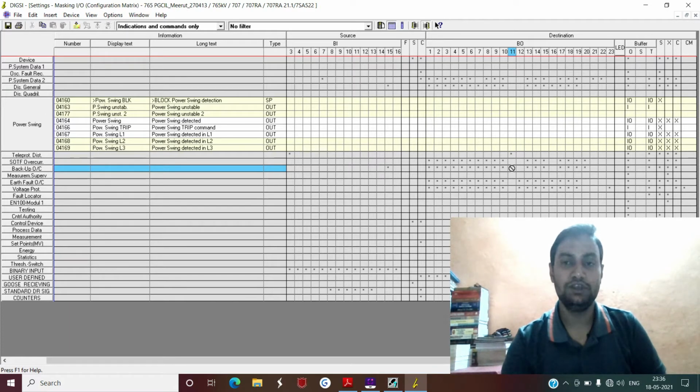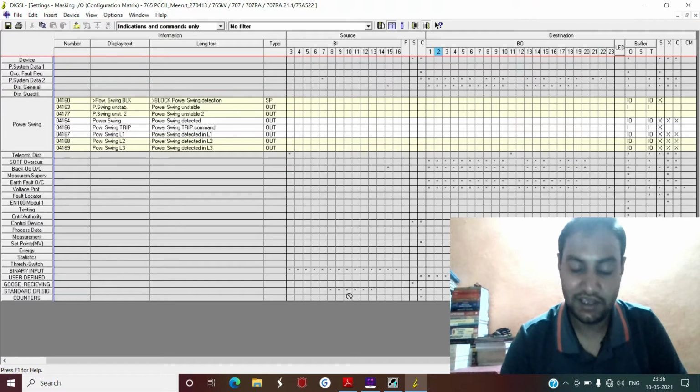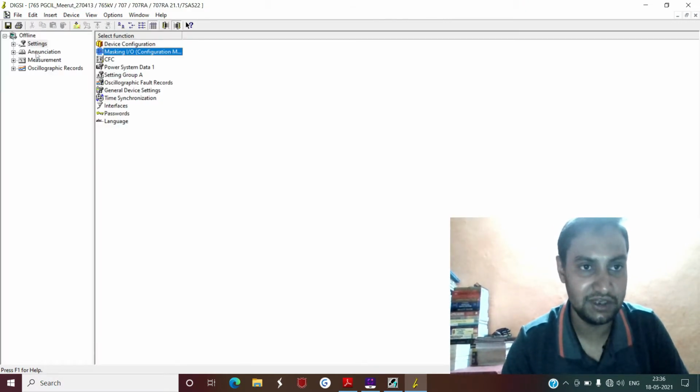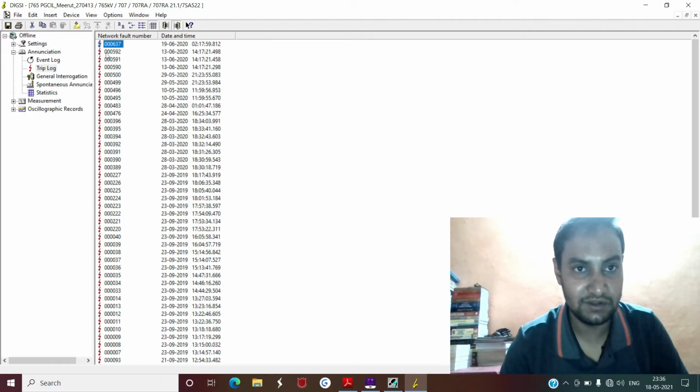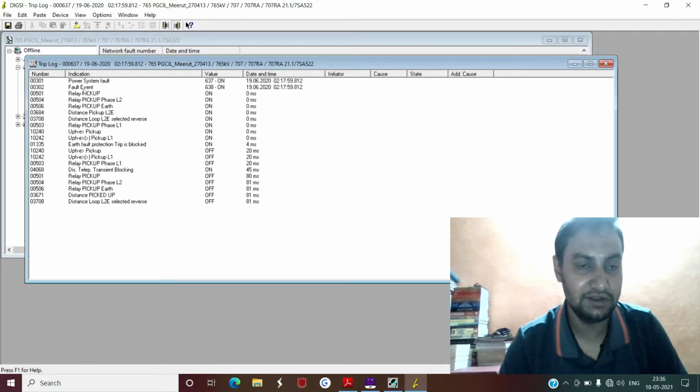Now, there are two things. One is your disturbance record, which is available to you as a part of oscillographic fault records. Another is that you can configure the signals of your distance protection relay in your trip logs, which are available here. If you see in the annunciation, I have already saved some of the trip logs from the earlier sessions. So, if you click this, now what you can see is that some of the signals are available.